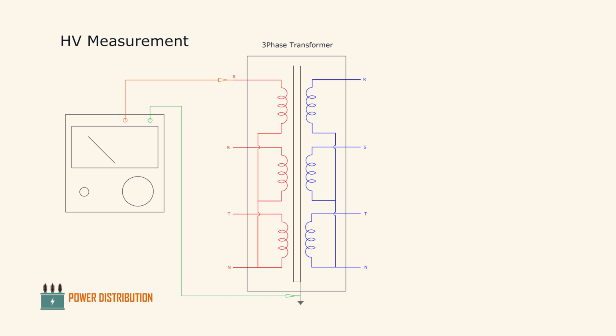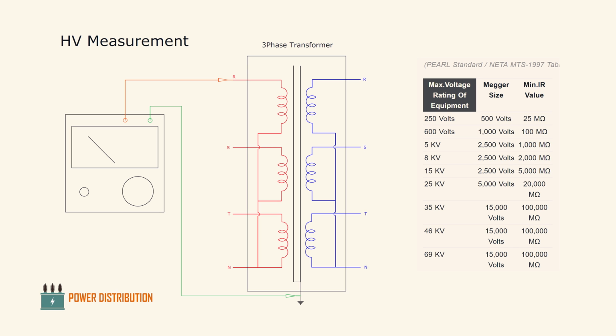In order to check the insulation level or condition of this primary bushing or the primary windings, we connect the line or the red probe of this measuring device into any of the primary terminals, and then we connect the earth probe or the green wire into the ground connection of the transformer. On the right, per standard, is the minimum insulation resistance value according to the voltage level that applies to this particular transformer. In our case, the system voltage is around 11.7 kilovolt, so the minimum insulation resistance should be around 5 gigaohms.